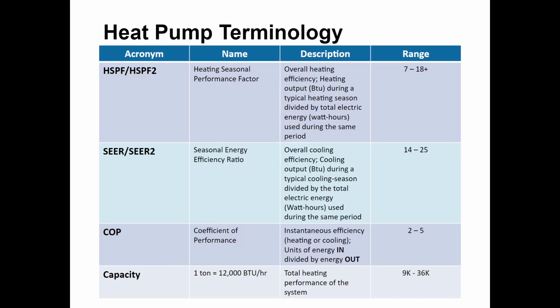We typically, in the deep south talking about air conditioning, throw around the words 1 ton or 2 tons of cooling. Here in heating climates like Fairbanks, we'll typically talk about BTUs per hour, and 1 ton is 12,000 BTUs per hour — the total heating performance of the system. A rule of thumb for a normal space that's not super well insulated is that 12,000 BTUs of capacity can condition 450 square feet of living space.